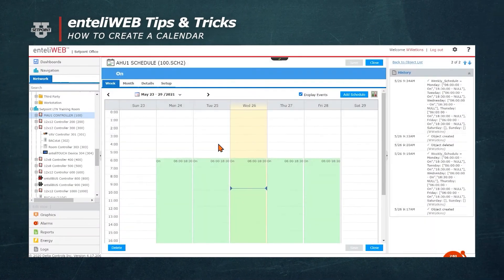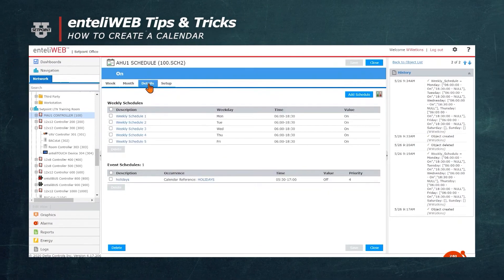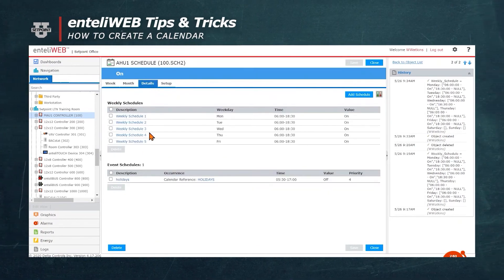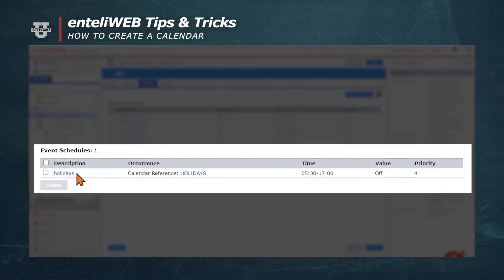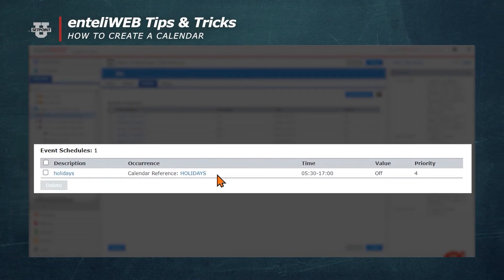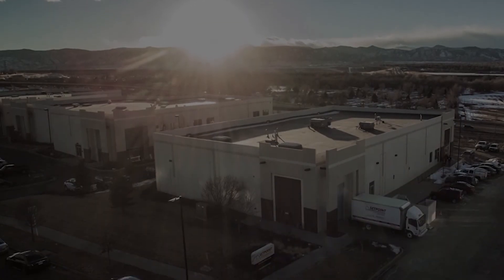Now, to verify that this calendar is now part of the schedule, we can go to the details. You'll notice that under the event schedules it says Holidays. And since it's a calendar reference, the time that it starts and stops are the values that we'll list as on and off.